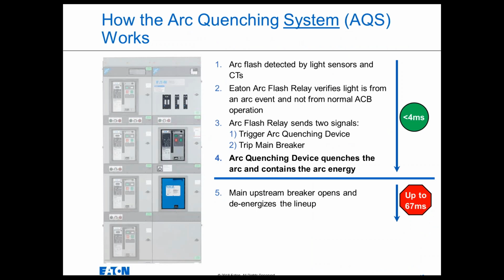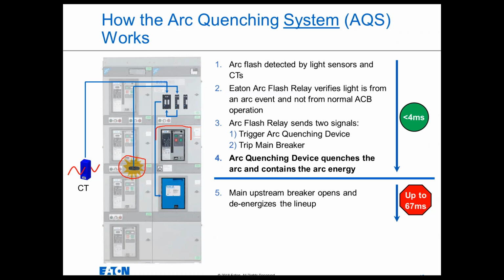So how does the arc quenching system work? First, when there's an arc flash, light and current are detected by the arc flash relay. CTs are actually mounted on the line side of the main breaker, and then point sensors, wired point sensors, not fiber optic, wired point sensors that are strategically installed throughout the switchgear pick up that flash of light. So light and current, when both those signals are sensed by the relay, that relay sends out 2 trigger signals. The first one goes to the arc quenching device and tells it to operate.